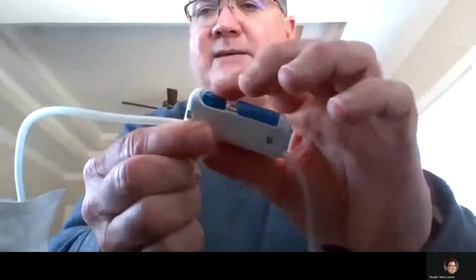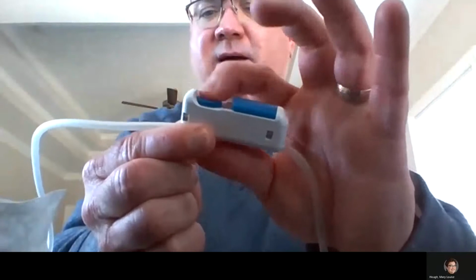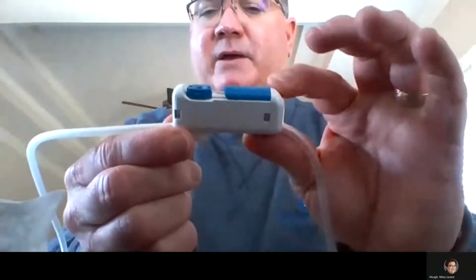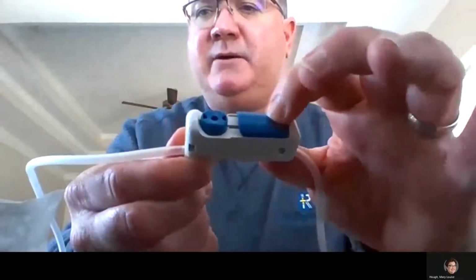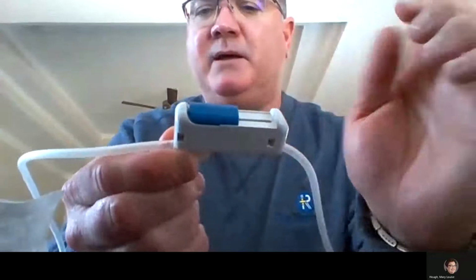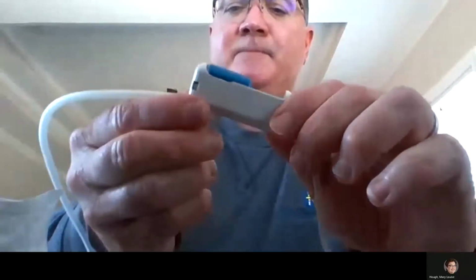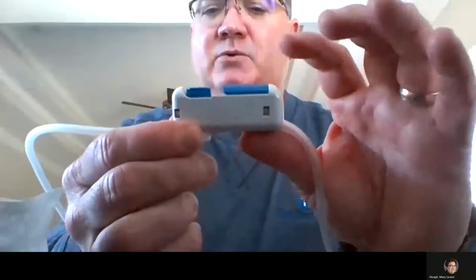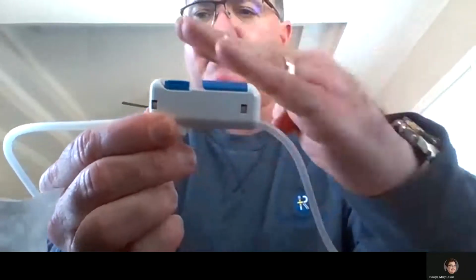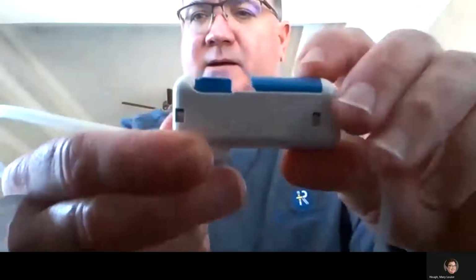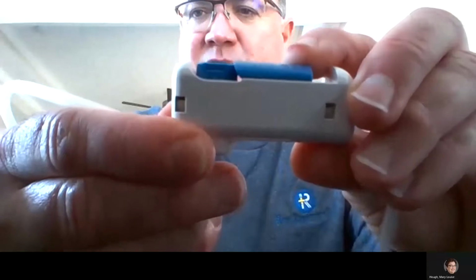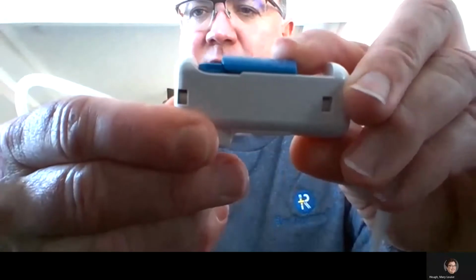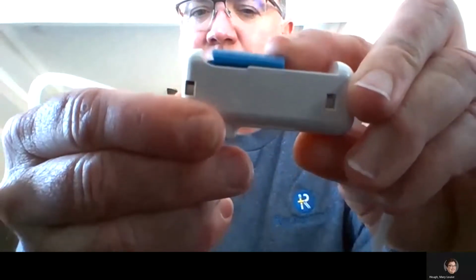So this allows you to adjust the flow rate and ease the patient into it. I can do that either by titrating, pushing a couple of times till the patient is comfortable. If they are comfortable, this little blue slider here can then be pushed up and lock that button down in place, and the flow will continue naturally. Another thing that I can do is this little blue slider is built on a ramp. So if I start to slowly push it forward, you can see that button slowly depress. And then once the patient is okay, I can then lock it into position and do the same thing.